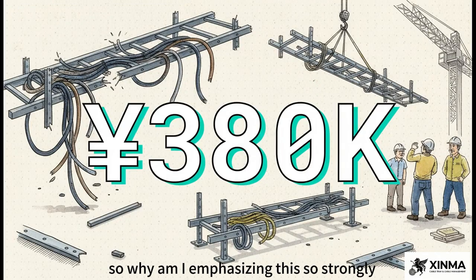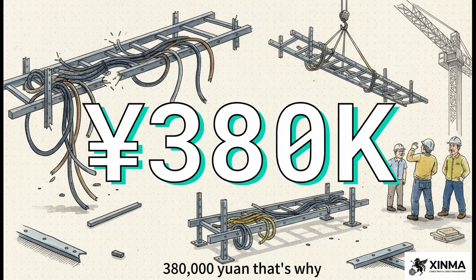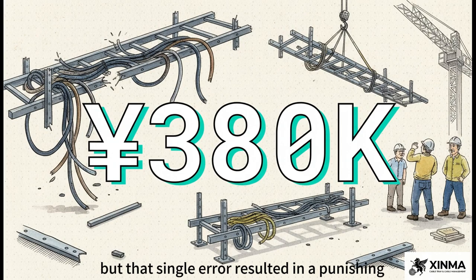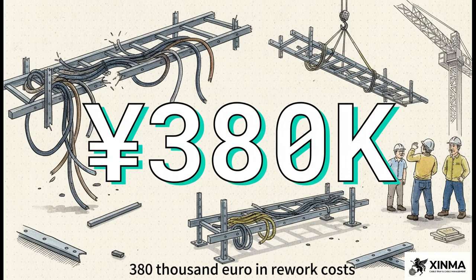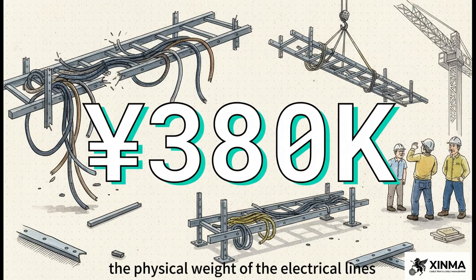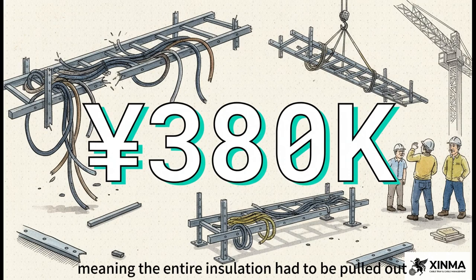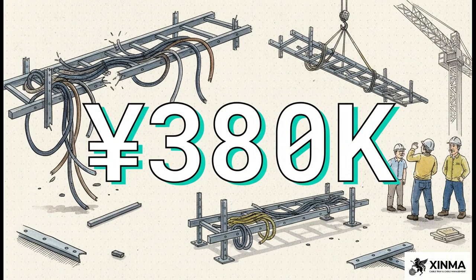So why am I emphasizing this so strongly? 380,000 yuan. That's why. On that exact same Shandong project we were just talking about, one specific section was undersized by just a single load class. Just one class down. It's almost hard to believe, but that single error resulted in a punishing 380,000 yuan in rework costs. The tray system literally couldn't support the physical weight of the electrical lines, meaning the entire installation had to be pulled out, scrapped, and totally replaced. It is a stark reminder for all of us that precision pays off, and guessing costs dearly.